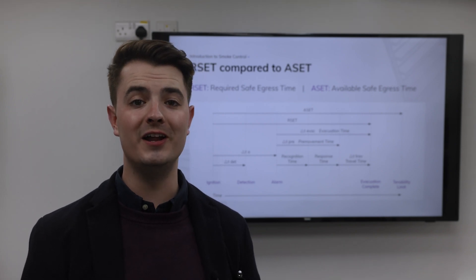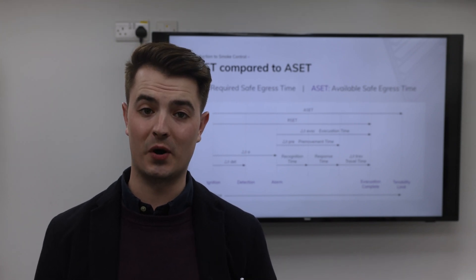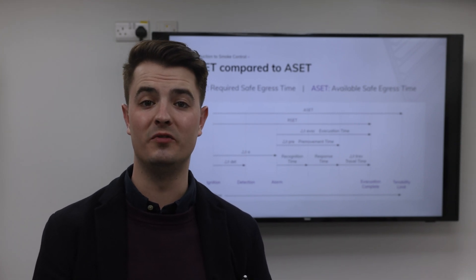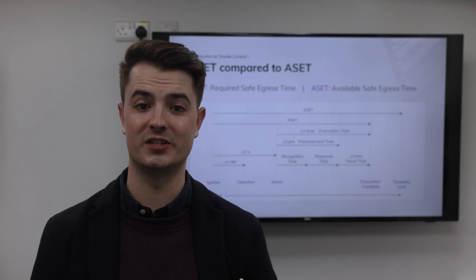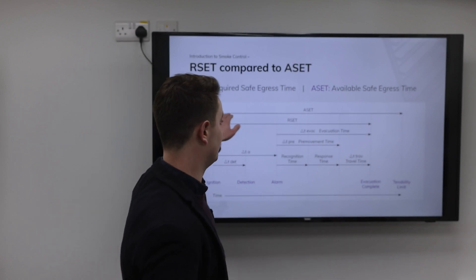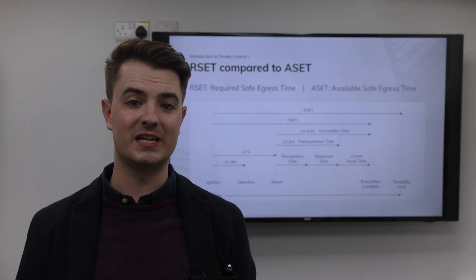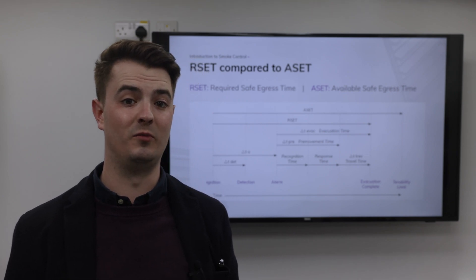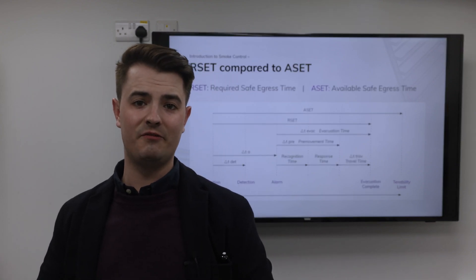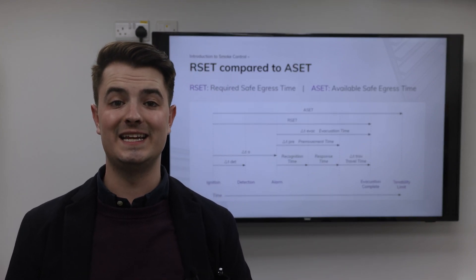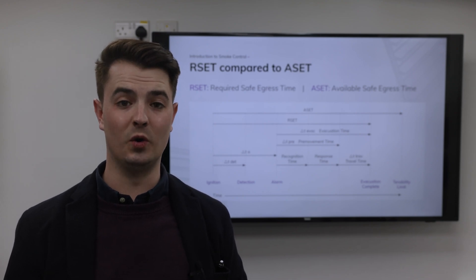ASET and RSET is a common fire engineering tool used to analyse the conditions in a building in the event of a fire. The basic aim of this approach is to show that the calculated time before conditions become untenable — which is the Available Safe Egress Time, or ASET — always exceeds the required time to safely evacuate the building, the Required Safe Egress Time, or RSET. If ASET exceeds RSET, then safe evacuation of the building is considered always possible.